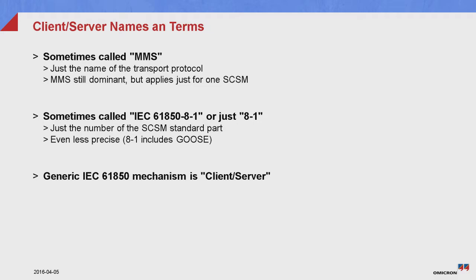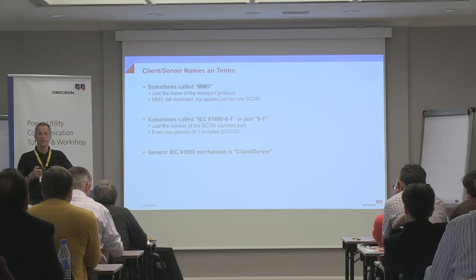And as I said, many people don't even use the term client-server. They just call it the MMS. But as I said, it's just a transport protocol. In principle, we could come up with another specific mapping, not using MMS, and we would still have client-server communication. By the way, these web services are exactly doing that.